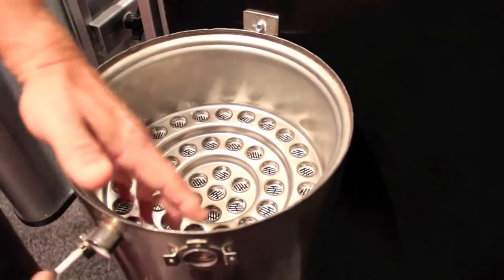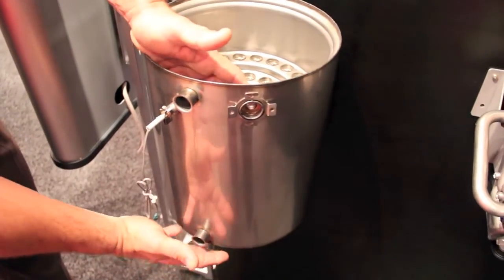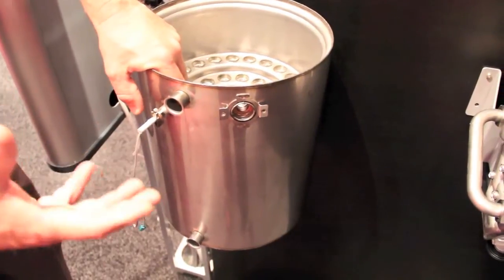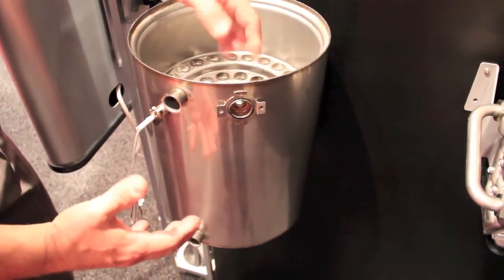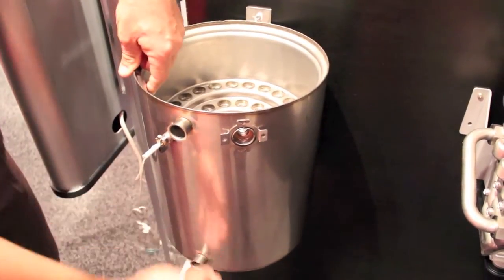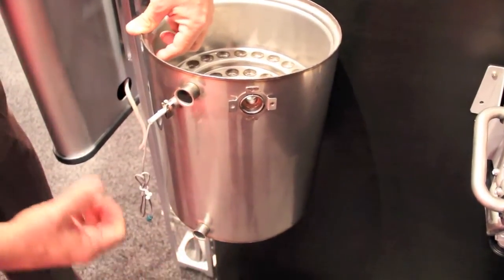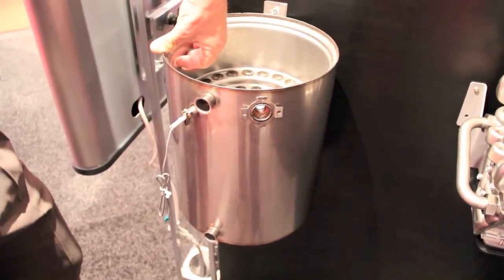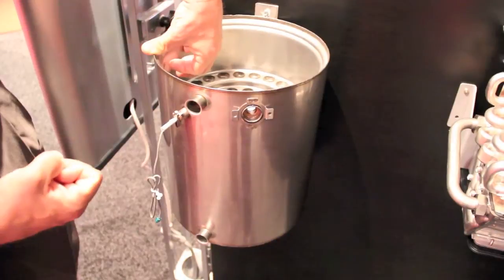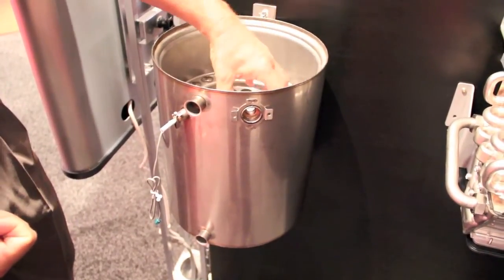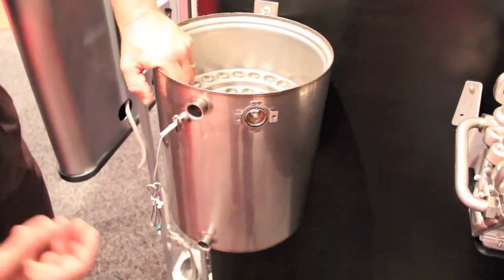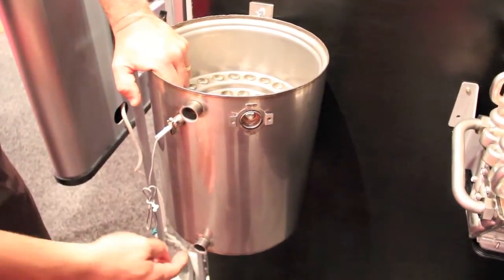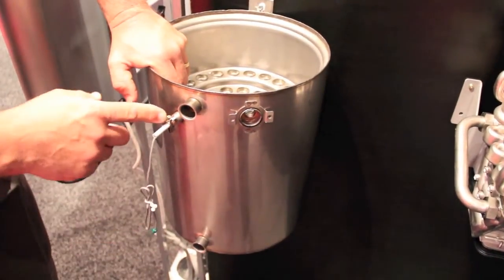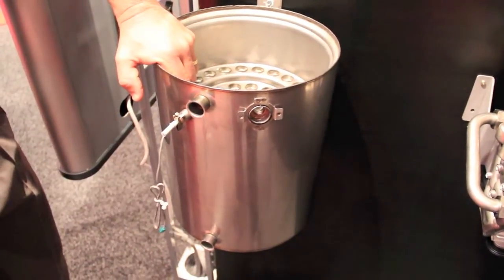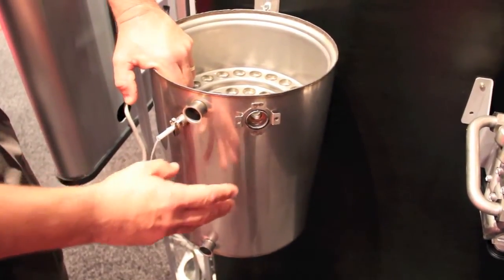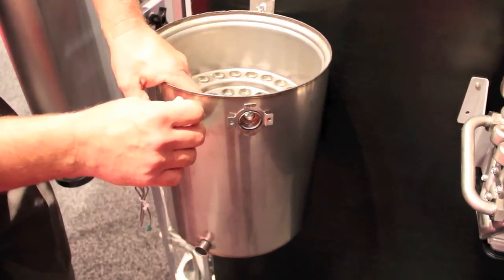If you pan back here, you'll see that the unit has some volume to it, so it's not susceptible to flow deviations and problems associated with flow because we've got volume there. And we're firing down through the module. We're trapping our condensate here, which is a highly efficient way to transfer the heated energy from the combustion system into the water, and also trap the condensate, which can harm heat exchangers long term. And then you have your inlet and outlet, your viewing port. They use a sensor here for a low water cutoff, which is really nice. And this is really the heart of the unit. This is the most important component in our EFT combis.